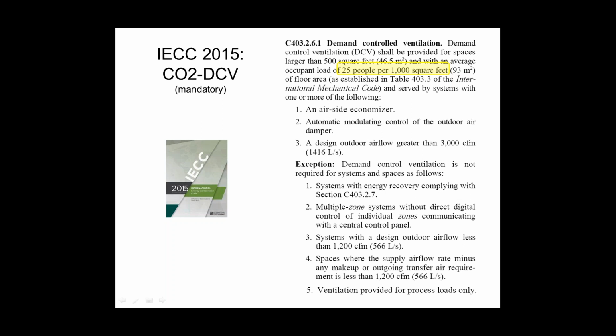Every damper for the spaces that require it. So that damper can be throttled back. And then the main air handler's outside air damper needs to look back at the zone dampers and see where they're positioned in order to decide what it's got to do on the other side of the equation. So sometimes a return air CO2 sensor may be prohibited. Sometimes it may be allowed, but even when it's allowed, it's probably not the best idea. People want to do it because they want to save first cost, but it really makes it impossible for you to throttle back the ventilation air.